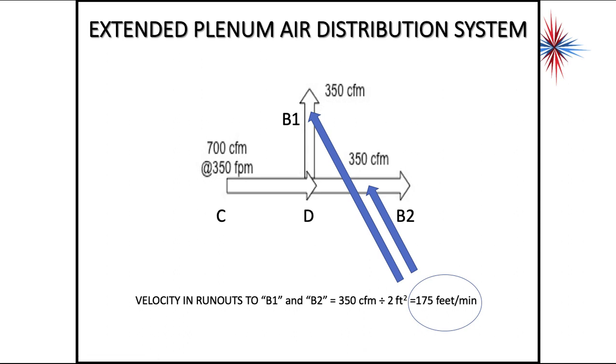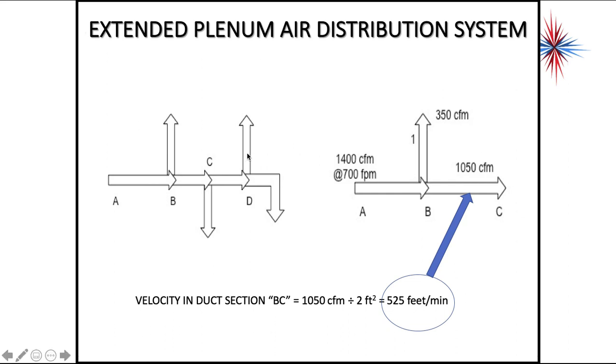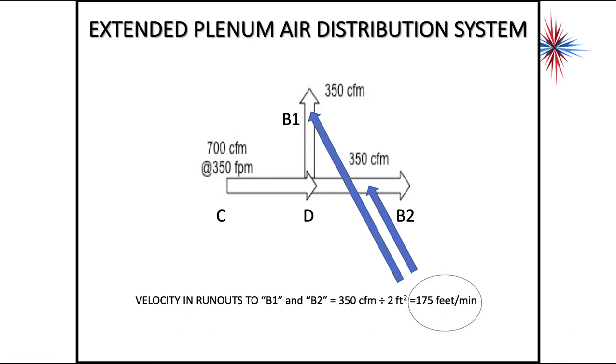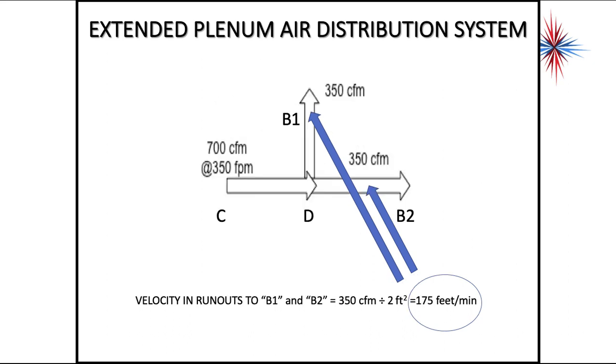So now we have the end of the duct reached. I have my, after my point D, I have the takeoffs for B1 and B2. So let's go back, I'll show you it here. We're talking these two takeoffs right here. So each of these is 350. So I have 700 CFM coming in, I have 350 going into B1, and that remains 350 for B2. So each of these, if I say this is a two square foot duct, 350 divided by two is 175 feet per minute. So B1 and B2 is all the way at the end of my duct system, and it's going to have very small velocities.